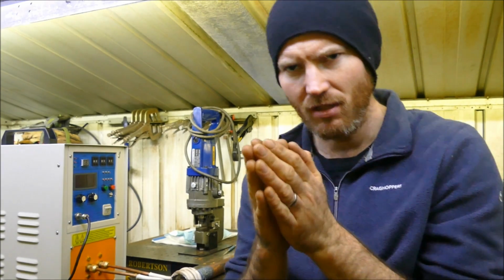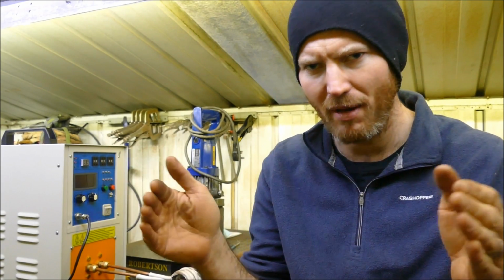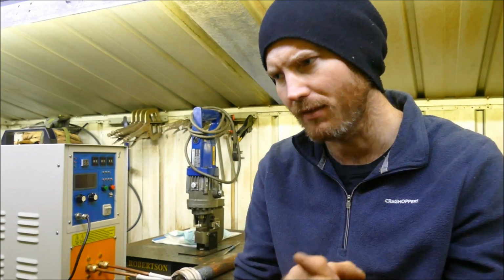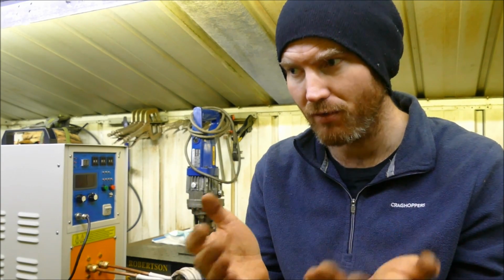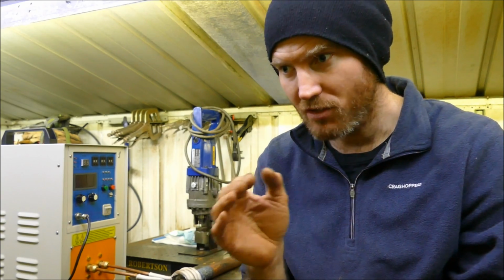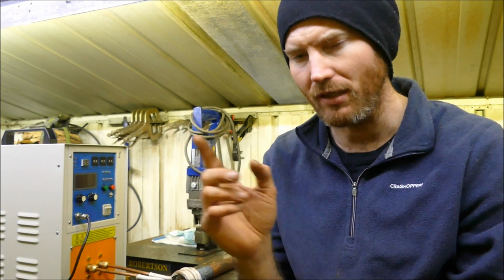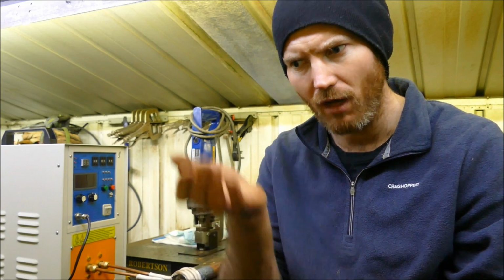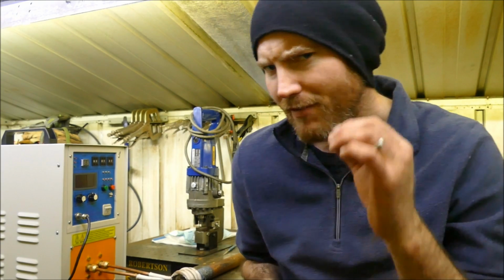My breakers are only rated to 32 amps, so it mustn't have been consistent enough over a period of time to trip the breaker. Maybe I haven't got the right breaker for it, maybe I need like a 63 amp breaker. But my breaker switch, I can't change because it's rated to all the wiring, so I'd have to change all the wiring to up the rating if it does trip it out. But I haven't tripped it yet.